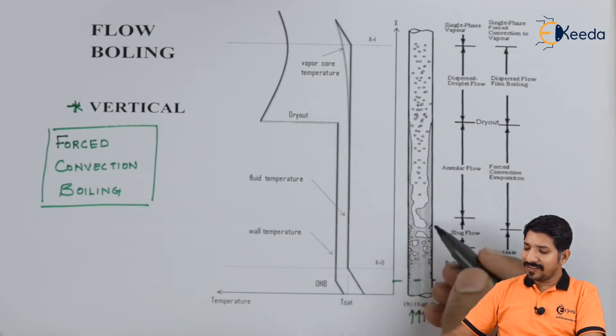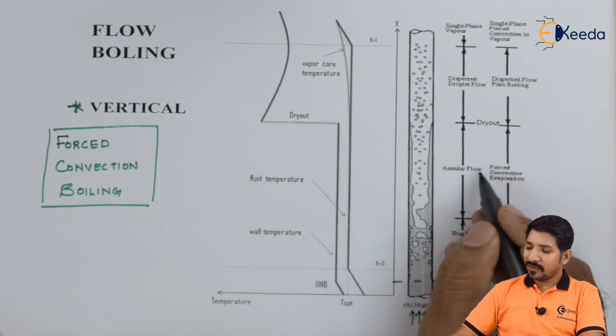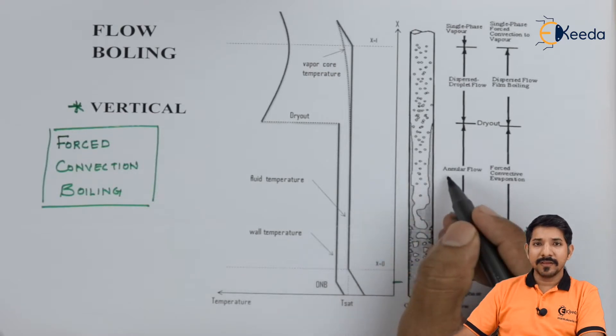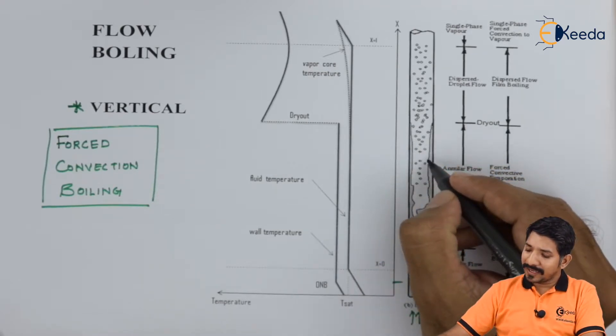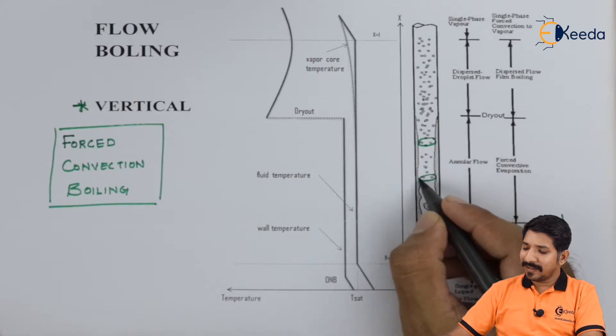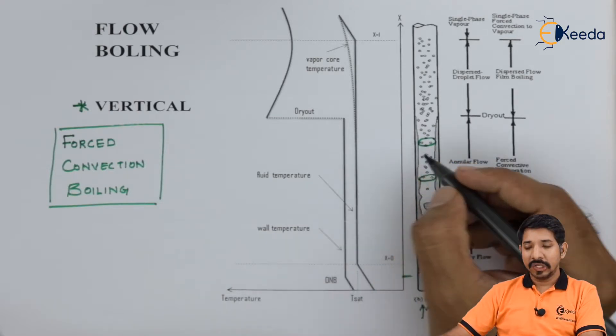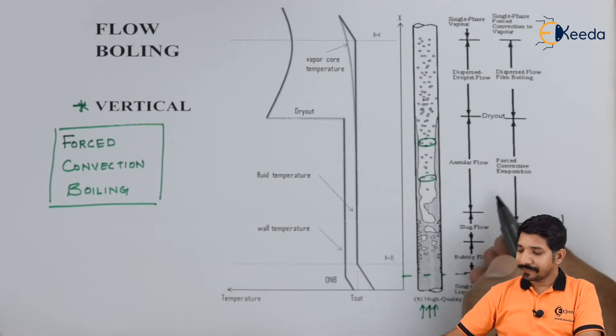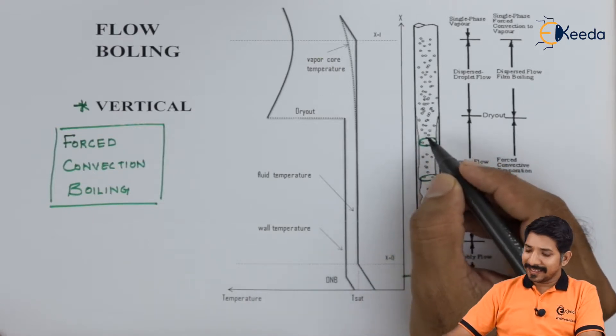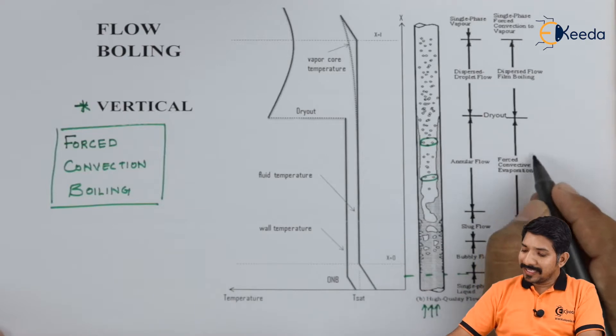After the slug flow, the slugs start collecting and form an annular flow. The annular flow gets its name because it looks like an annular ring. The annular ring diameter keeps increasing as we move upward. In this annular region, small droplets are present in between, and only a thin layer of fluid covers the wall of the tube. Heat transfer is predominantly by forced convection evaporation in this region.